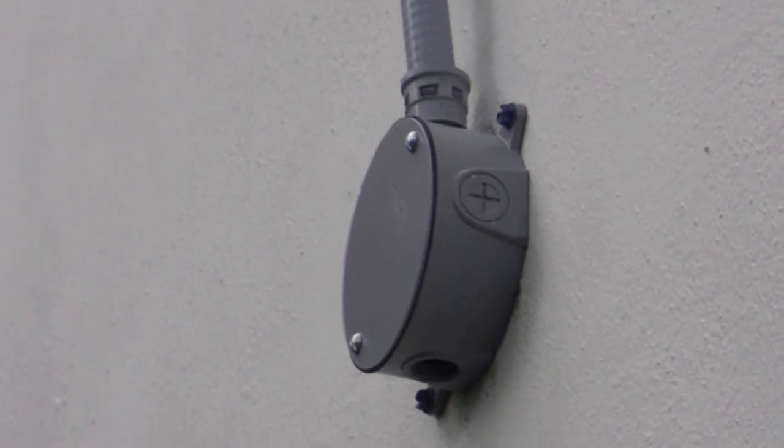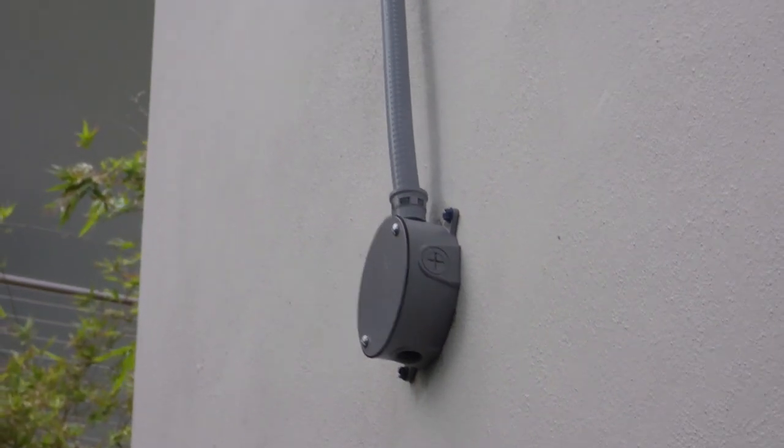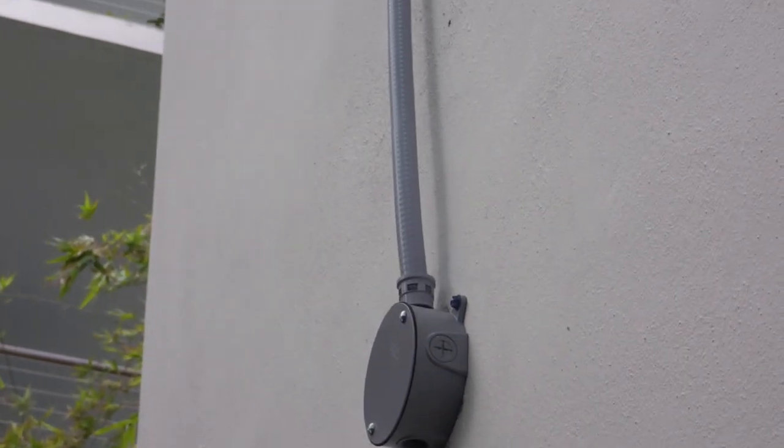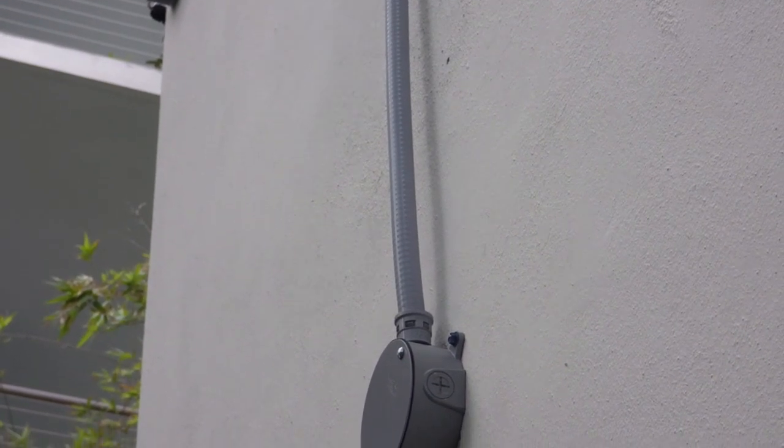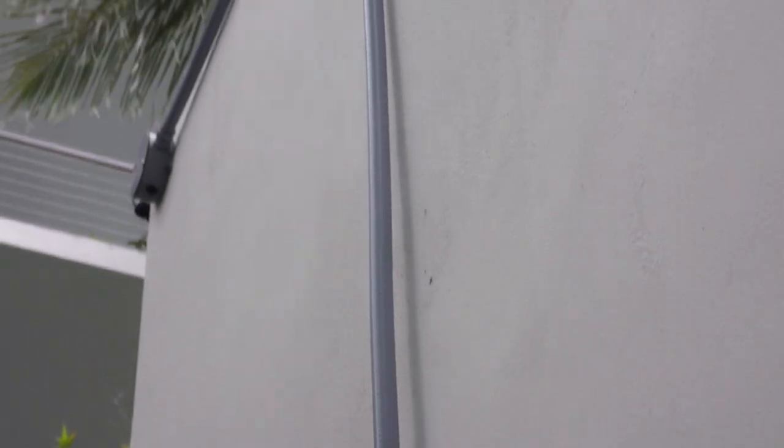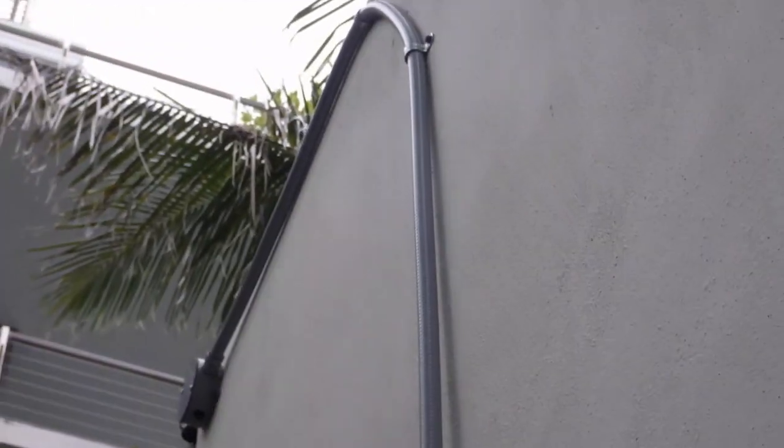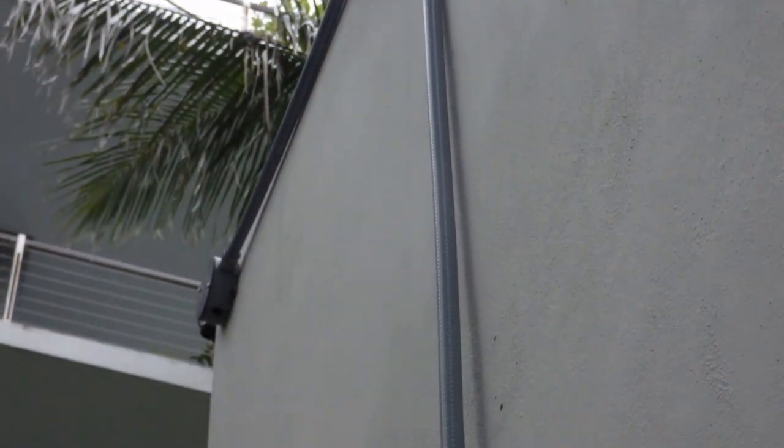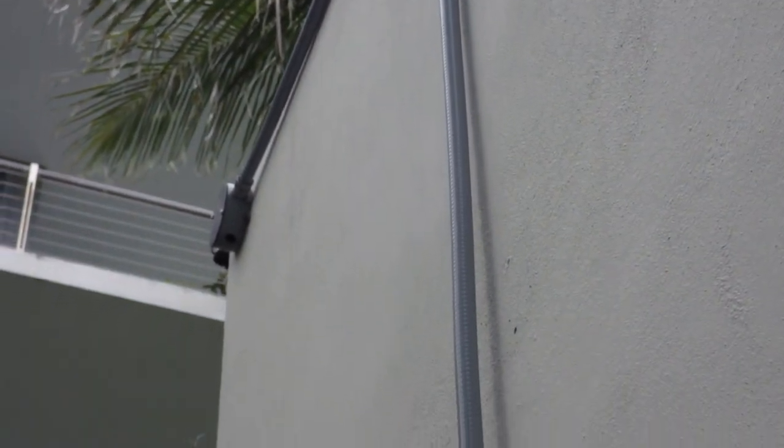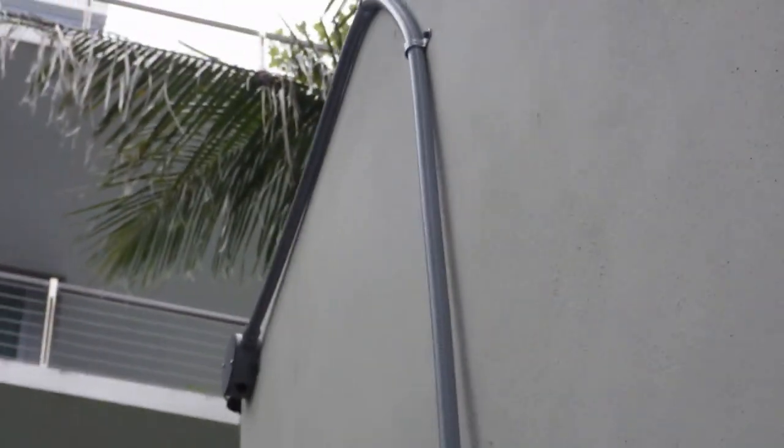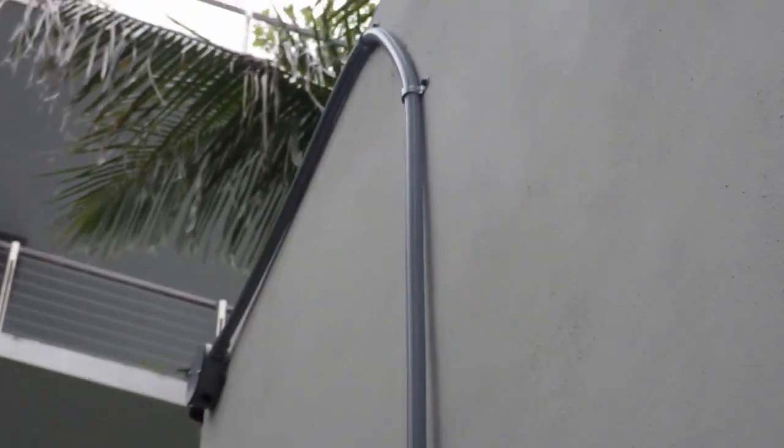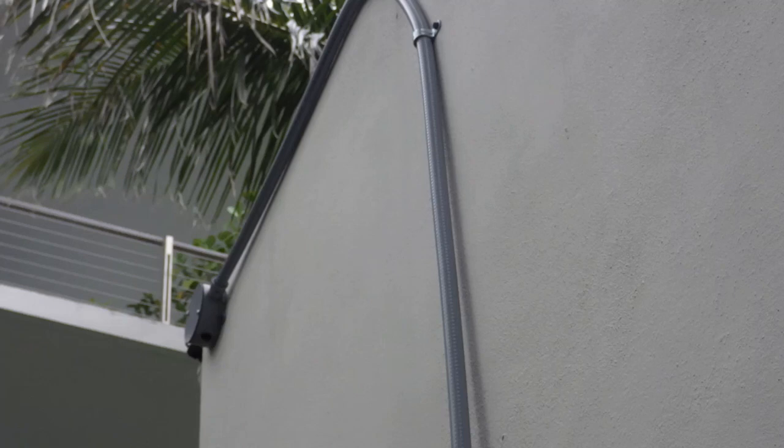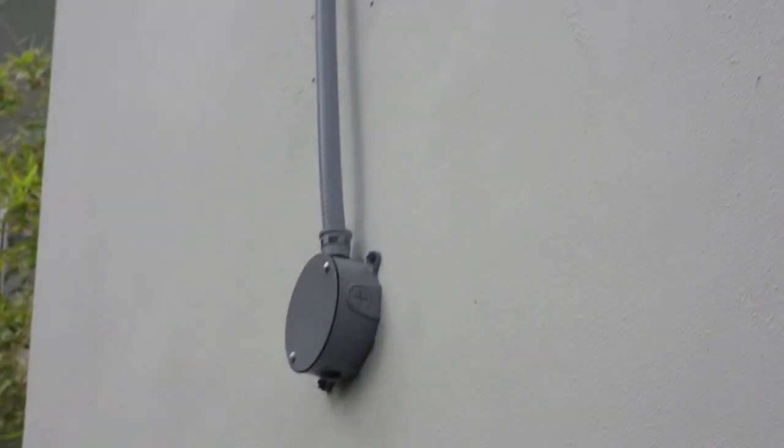This is liquid-tight flexible non-metallic conduit, but that's an ENT connector. And if we follow this up to the other box up there, also another ENT connector. You can't use ENT connectors with liquid-tight flexible non-metallic conduit.